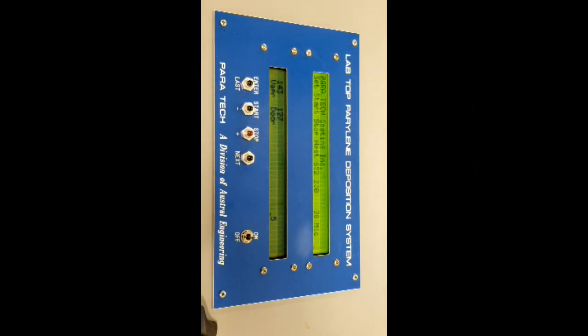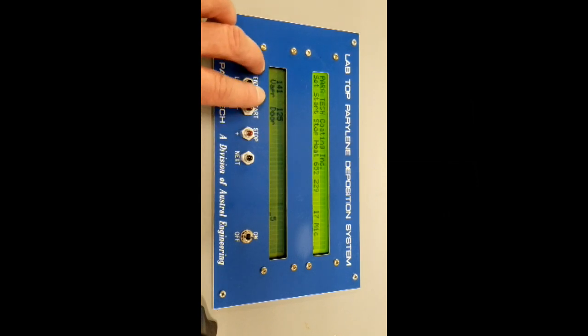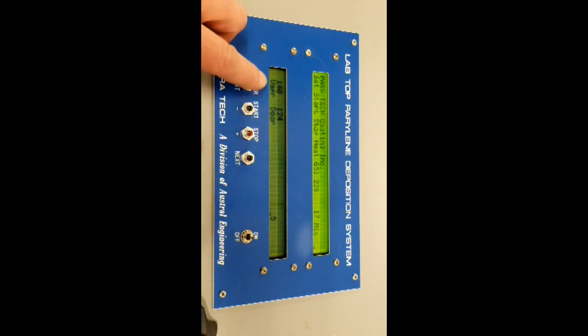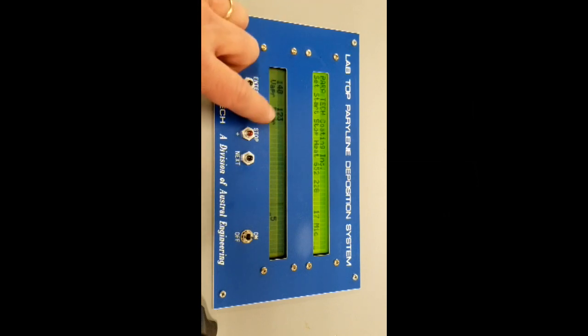Okay, that's it. The recipe has ended. Just one thing to point out, the vaporizer and the door, for some reason in this program, are reversed. So the temperatures are correct, it's just the labeling. This should be door on the left and vaporizer on the right.